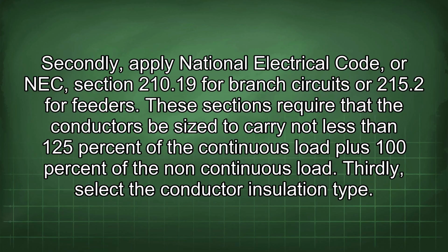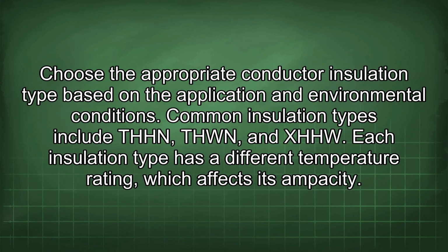These sections require that the conductors be sized to carry not less than 125% of the continuous load plus 100% of the non-continuous load. Thirdly, select the conductor insulation type. Choose the appropriate conductor insulation type based on the application and environmental conditions. Common insulation types include THHN, THWN, and XHHW.